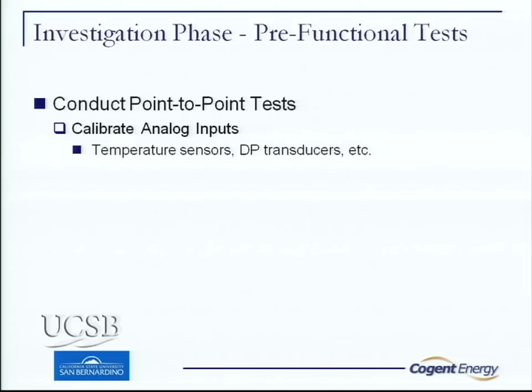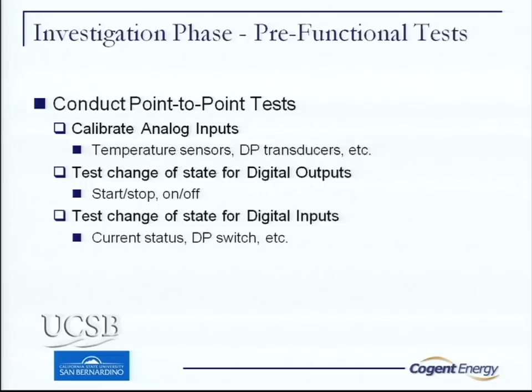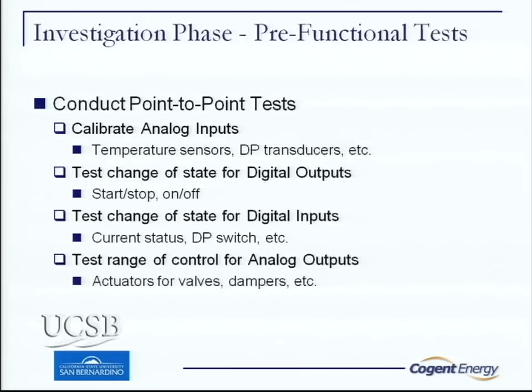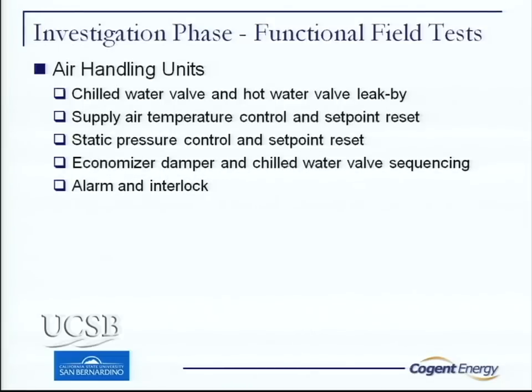We did our point-to-point — a group effort between Cogent staff and our staff — basically checking out the system and making sure it's doing what it's supposed to do. We corrected things like a flow meter issue, and temperature sensors that were out of calibration.